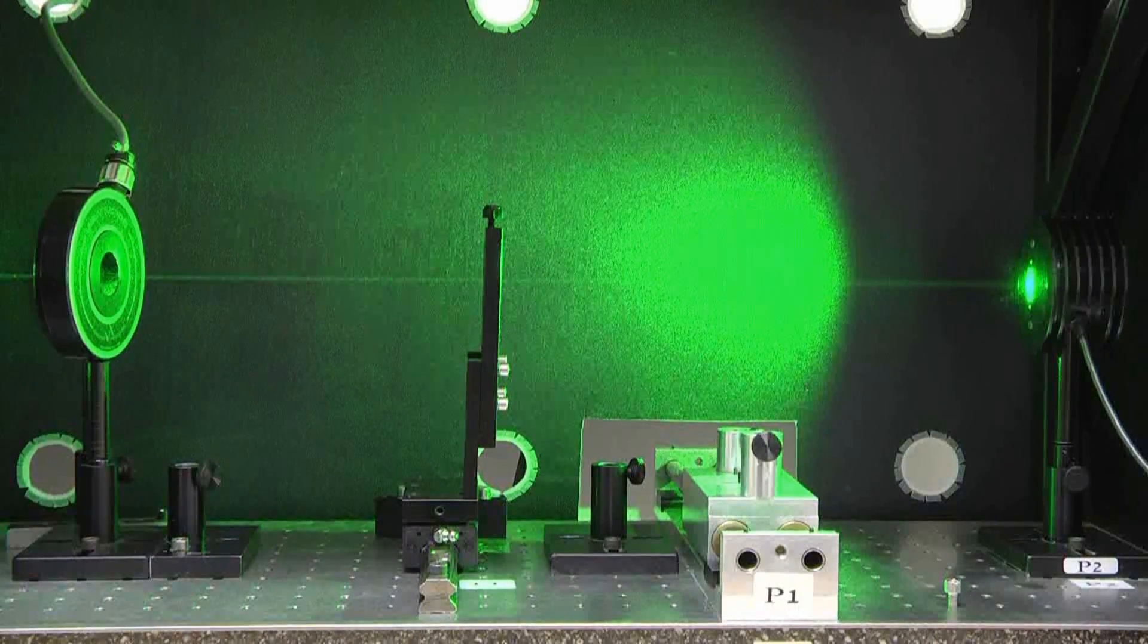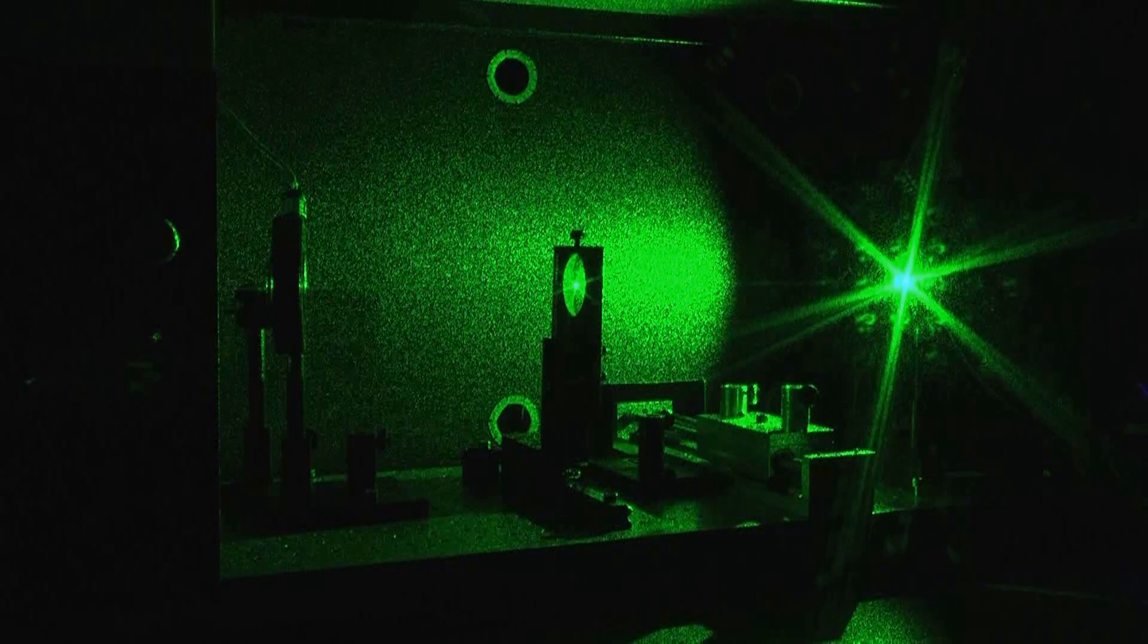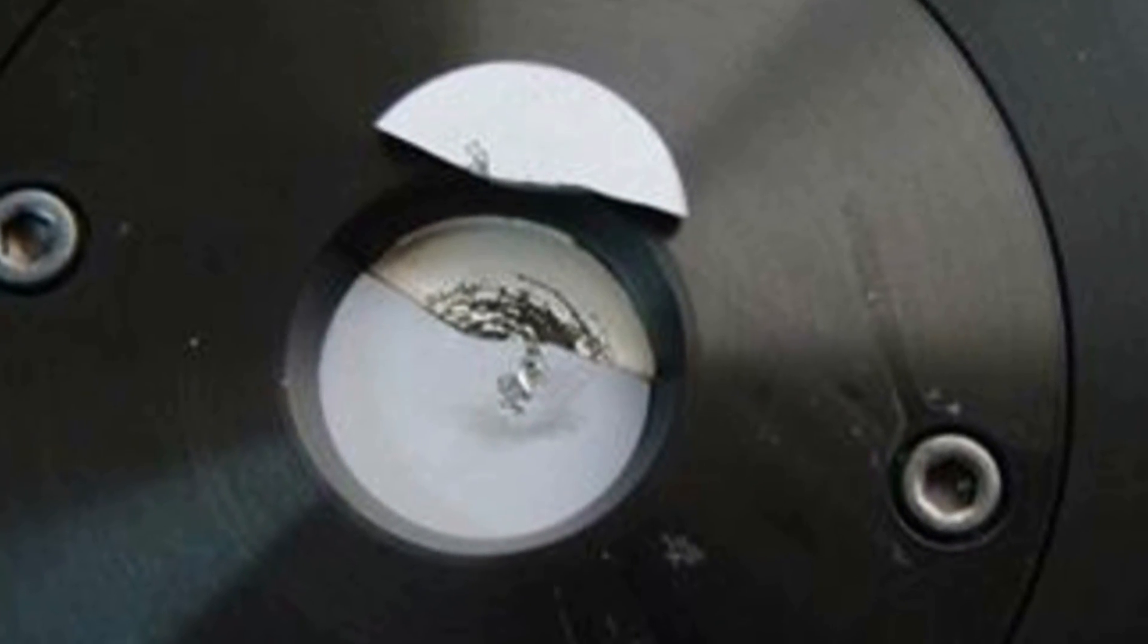Occasionally, a laser beam with a particularly high power or energy density can cause a visible burn mark on the absorber's surface of a sensor. If the absorber's surface is obviously damaged, then the sensor will need to be sent into a service center for repair.